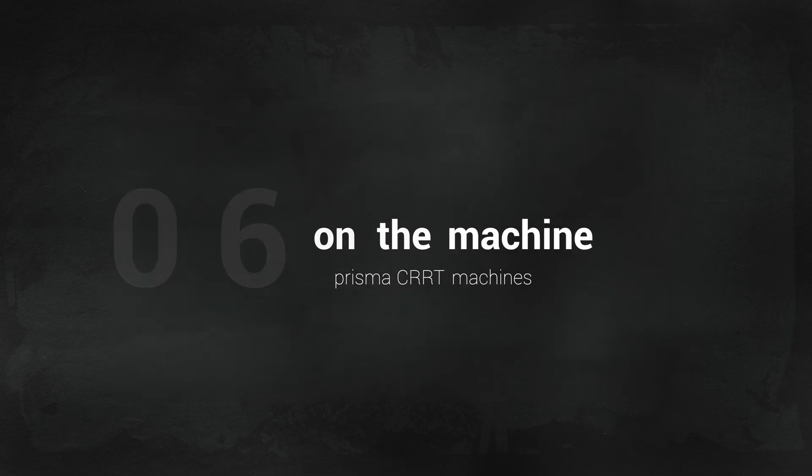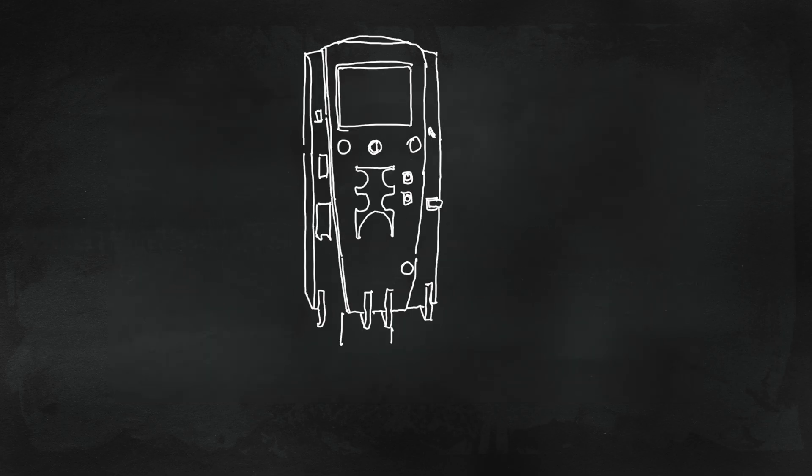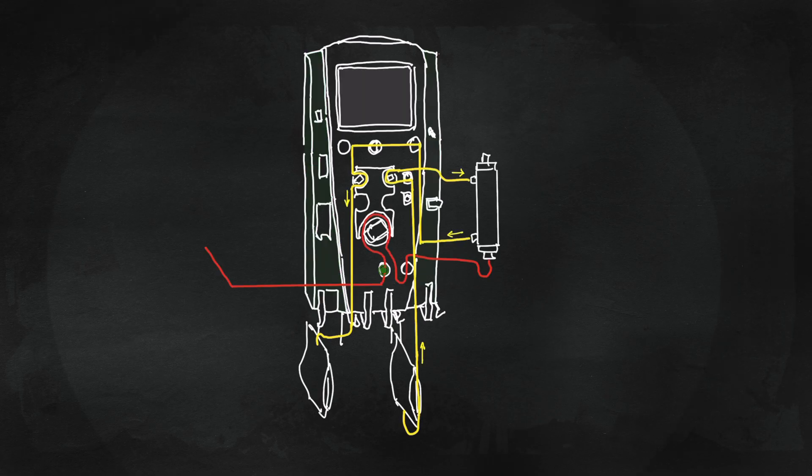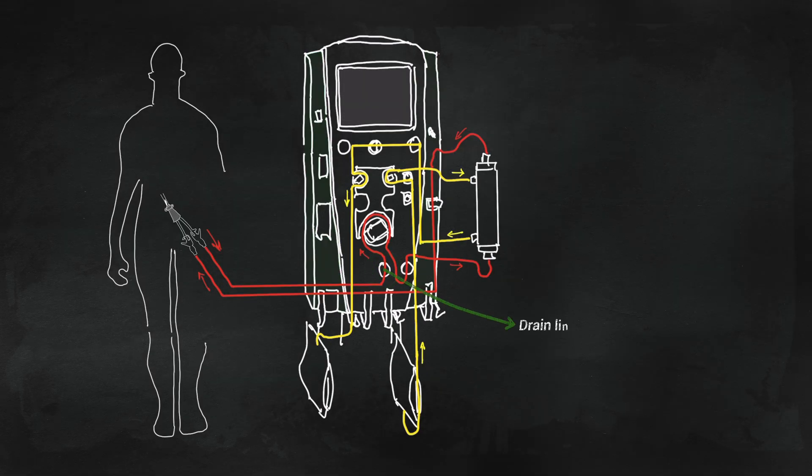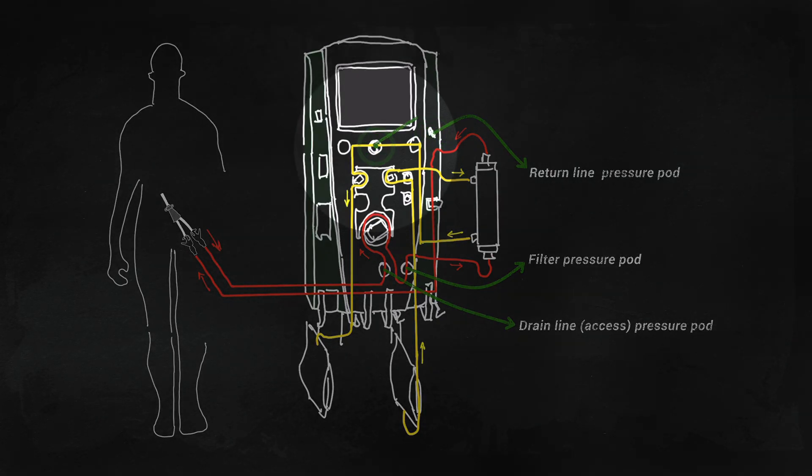We'll use the Prisma CRRT machines to point out the pressure pods that we have discussed. There's the access pressure, filter pressure between the pump and the filter, return pressure, and the effluent pressure pods.